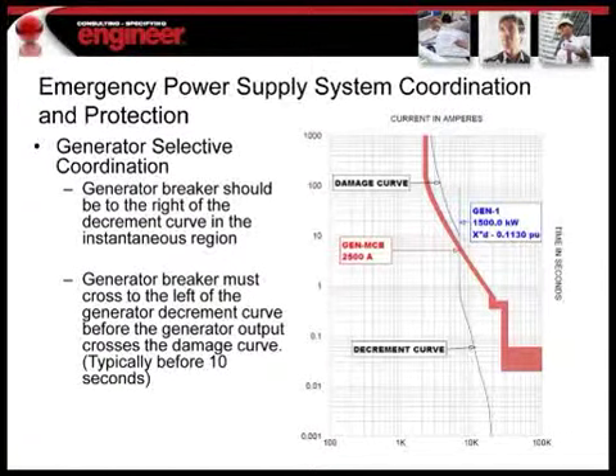So what we do is, if you look at this example, we're on the right side up until somewhere around 8 seconds, and then we jump across to the left side, which means that we're allowing the fault to happen, and we're allowing the generator to produce all that fault current until we get to that 8 seconds, and then we're protecting the generator. We're making sure that if the downstream breakers have not tripped at that point, that generator is not going to get damaged, and we're going to protect it at the generator. Where exactly that crosses is obviously an engineering judgment and decision. A lot of times it'll depend on what you have downstream and what you're coordinating with, how big your system is, and the components downstream. So that's pretty much a typical example of a coordination of the generator.